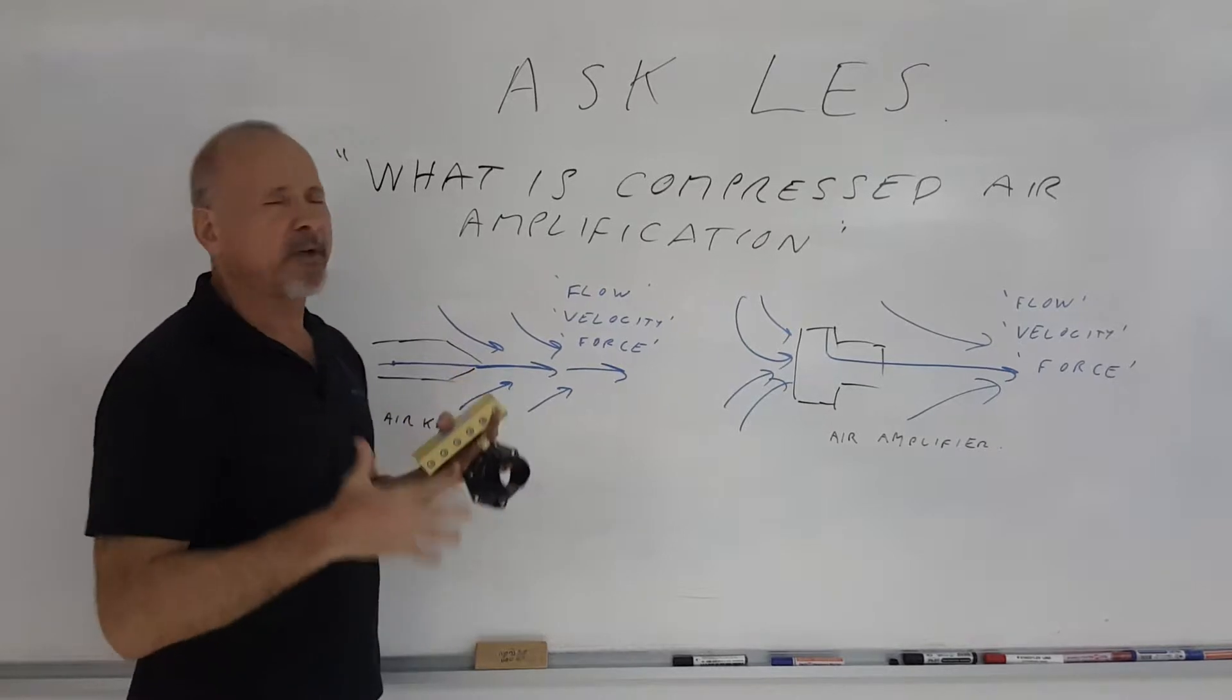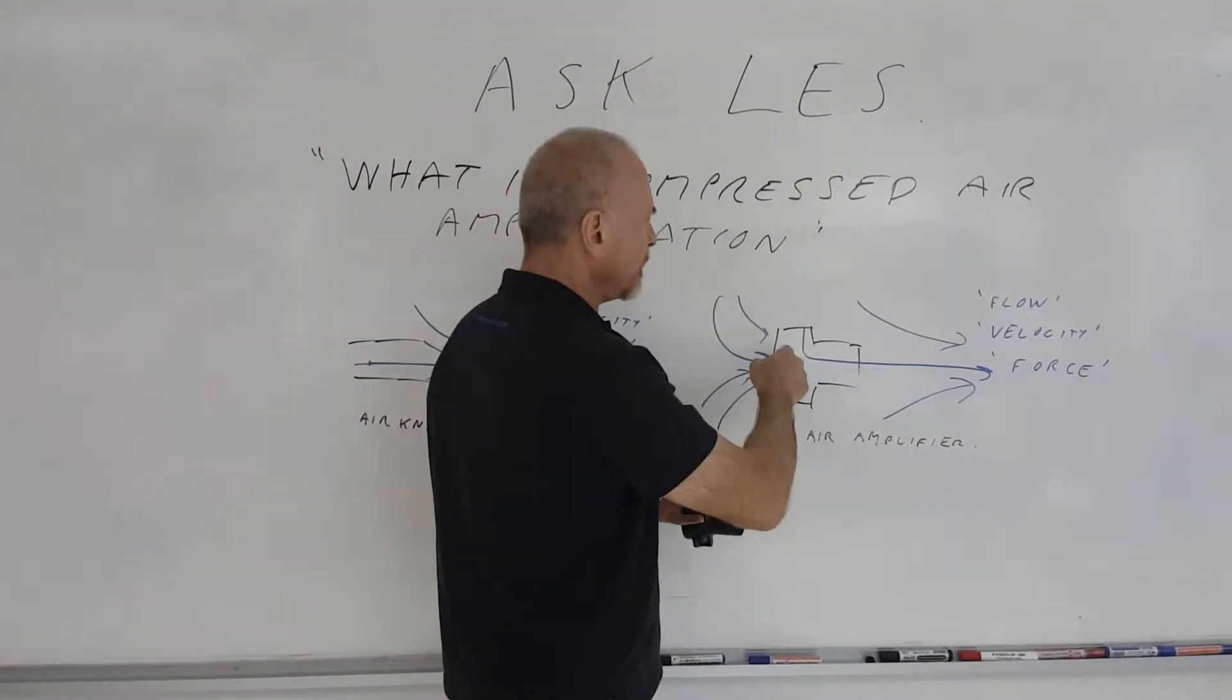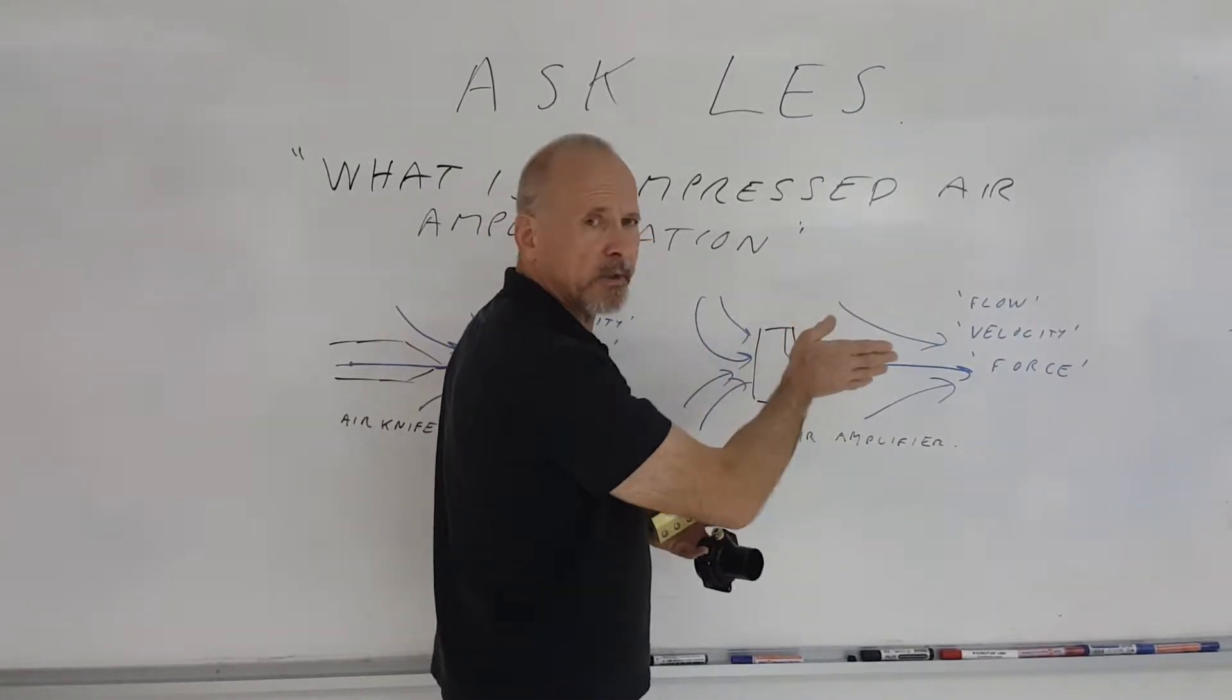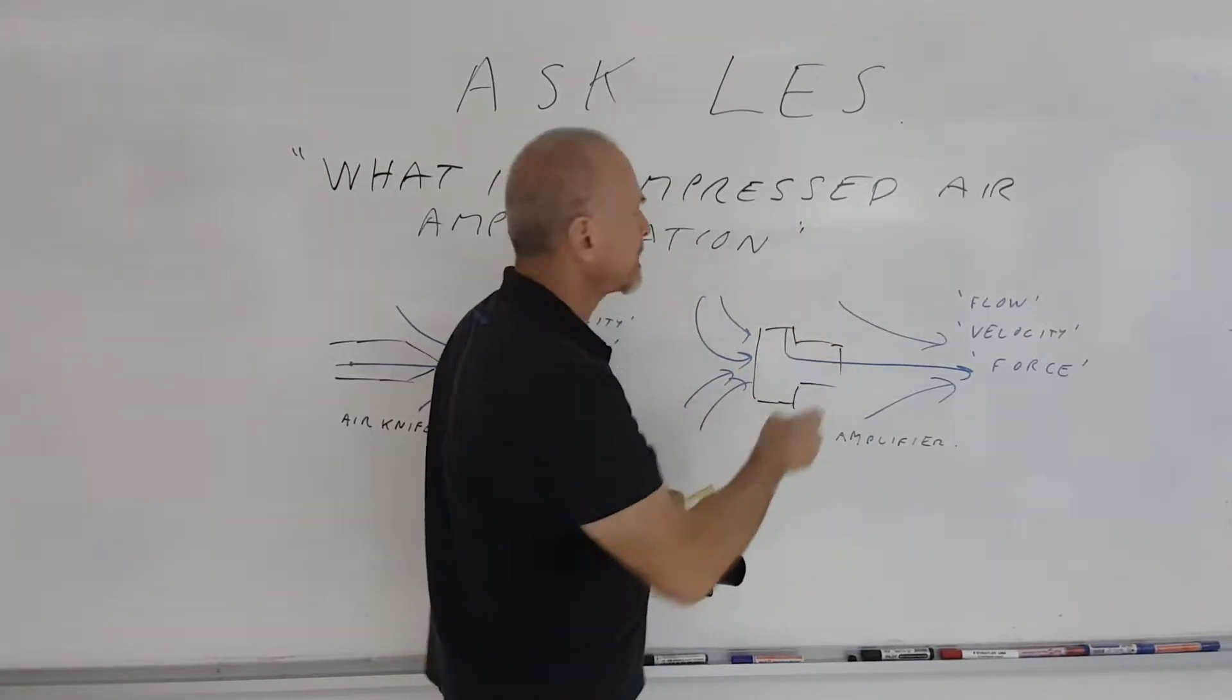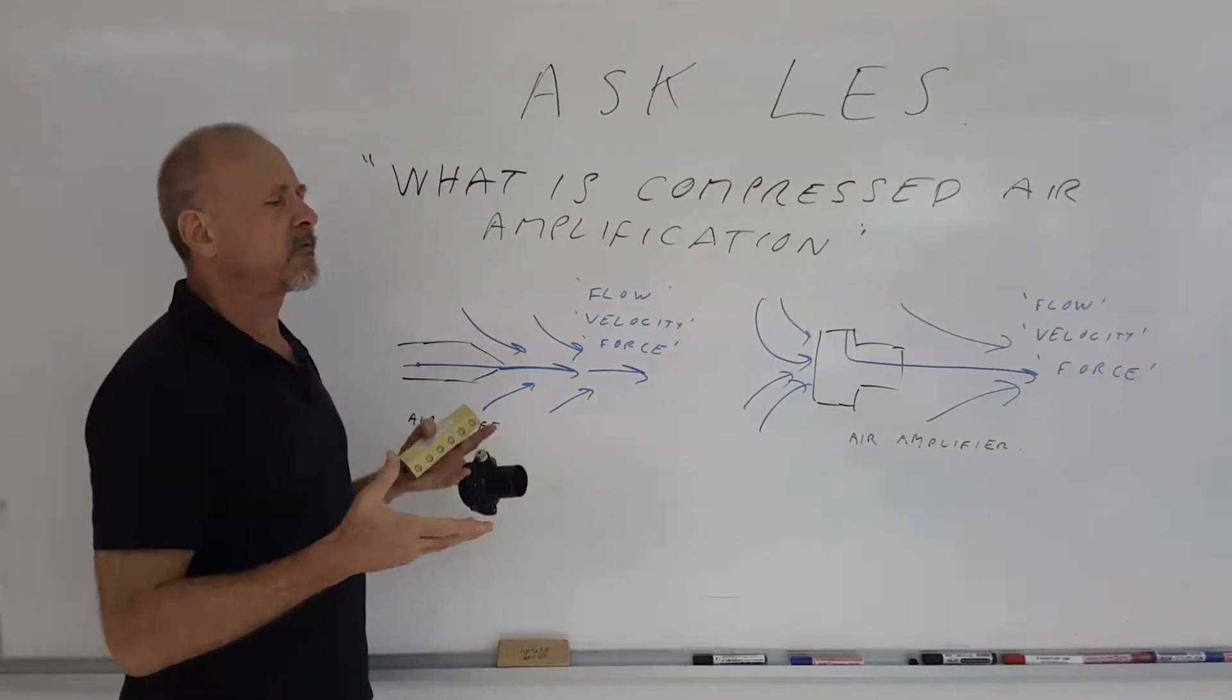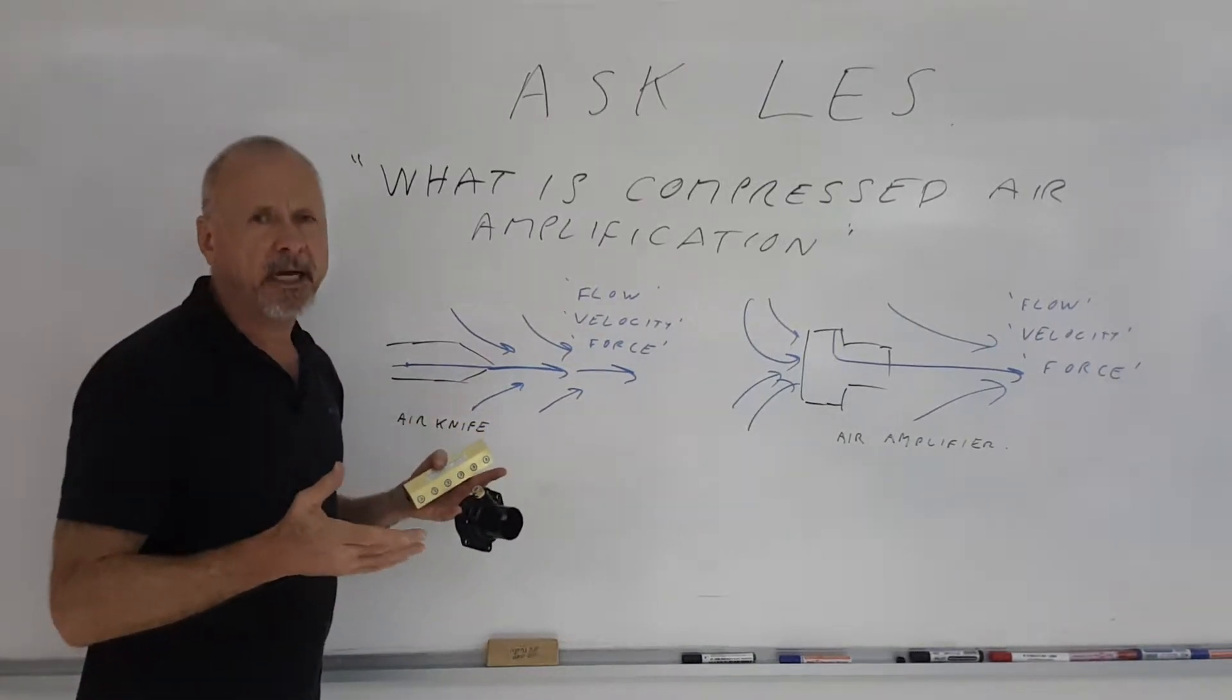What the amplification really is, is the difference between the compressed air used and the flow from the regular compressed air by itself versus the flow after it mixes with the surrounding air and amplifies it. Typically an air amplifier can amplify flow anywhere from 6 to maybe 15-16 times for effective amplification.